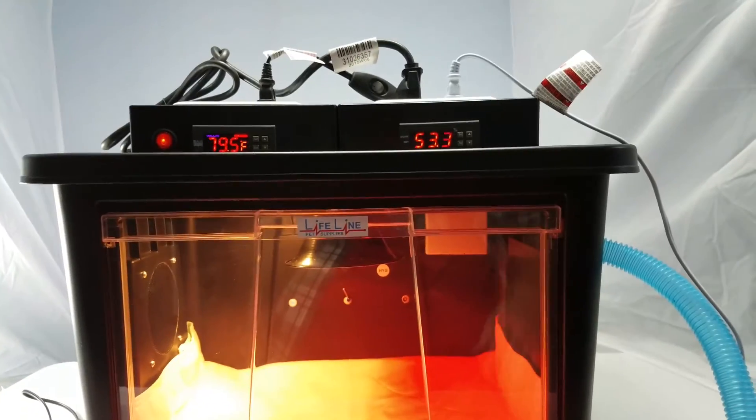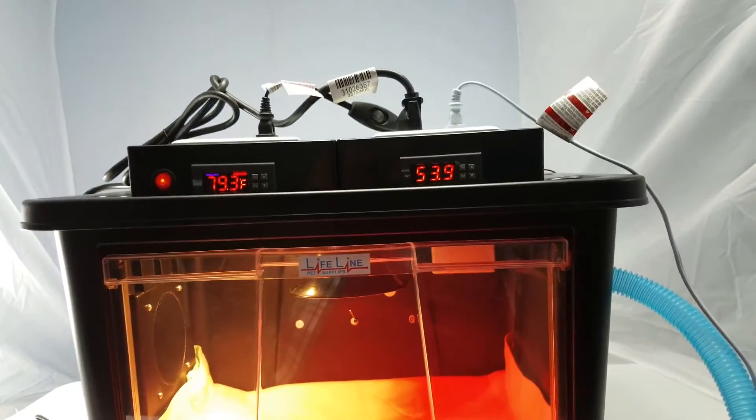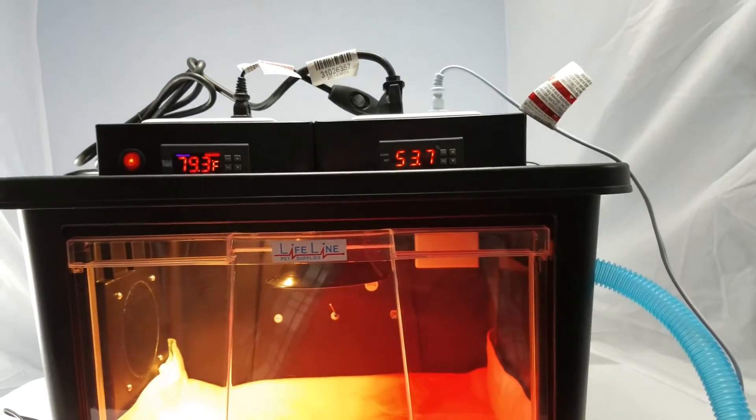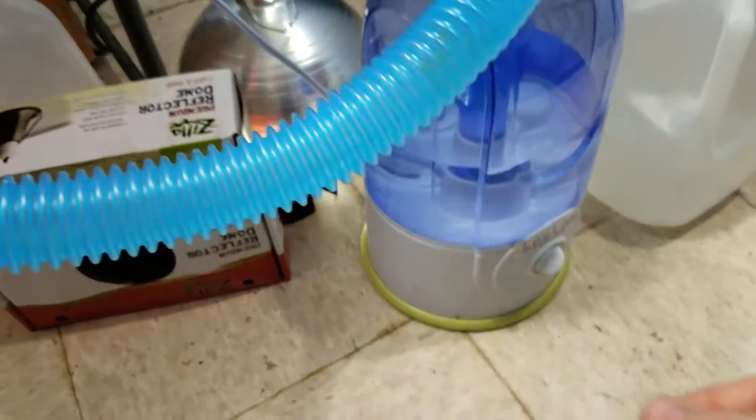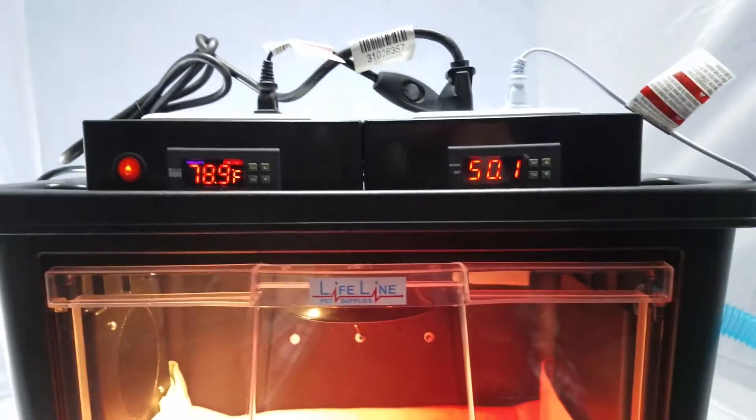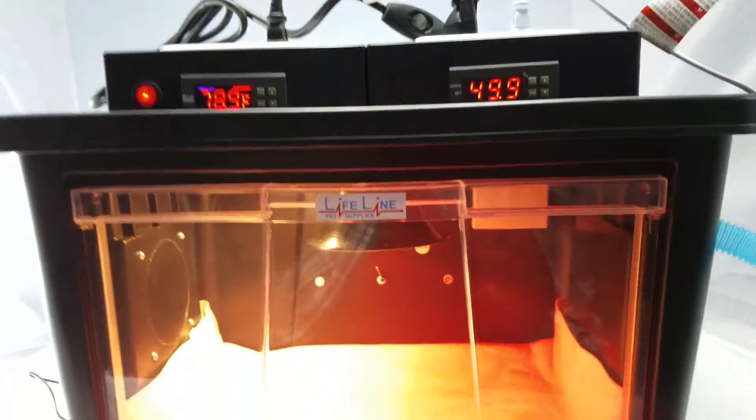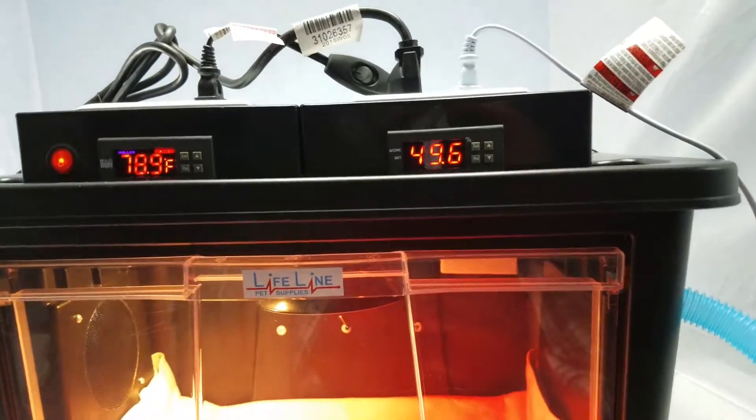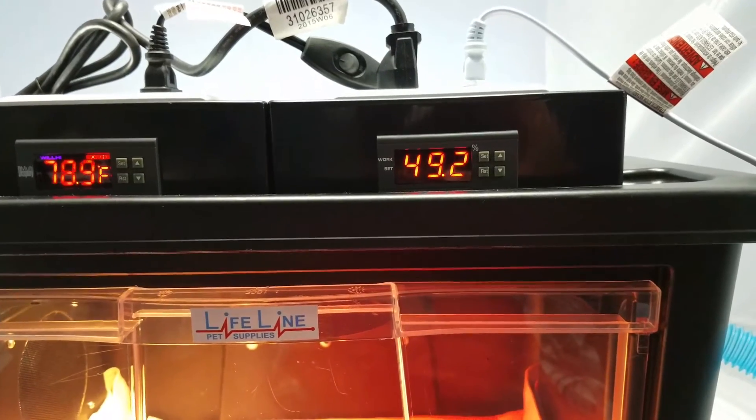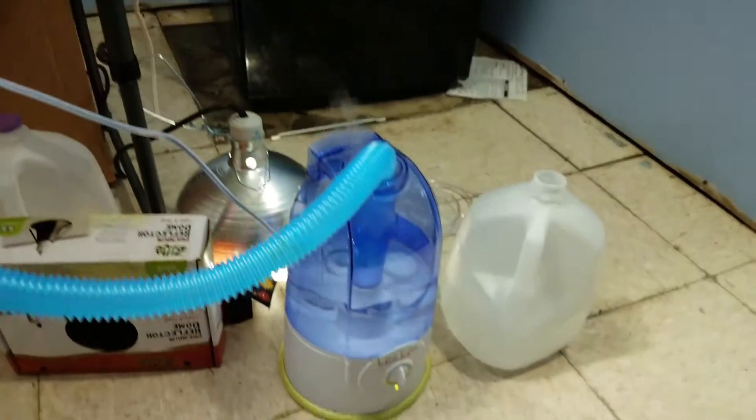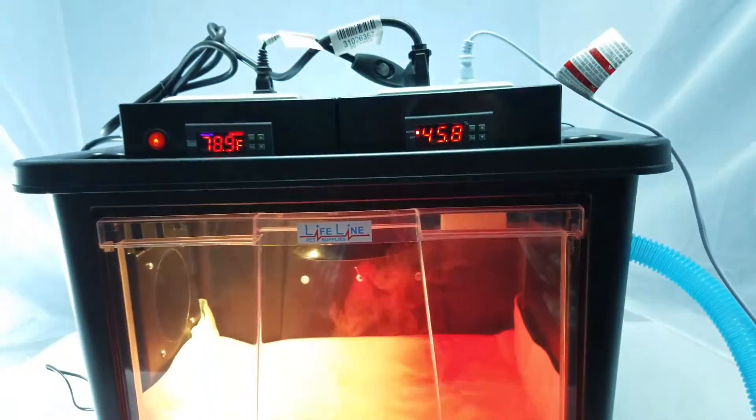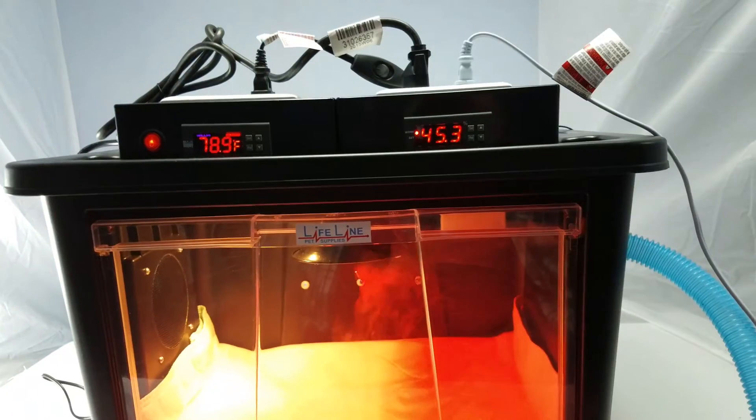You're going to get a little bit of fluctuation in it before it begins to come back down. And what you want to do to minimize that fluctuation is just to go to the dial on your humidifier, just turn it back just a little bit until you see the least amount of fluctuation out of it. And when that goes one percent below at 49, you'll see the light kick on, and now the pump kicks back on. There's the light on the pump, and it's pumping humidity back into the unit again, and it'll begin to rise.